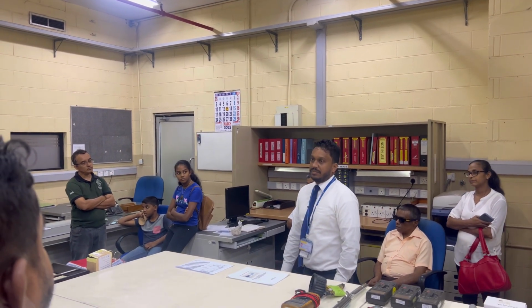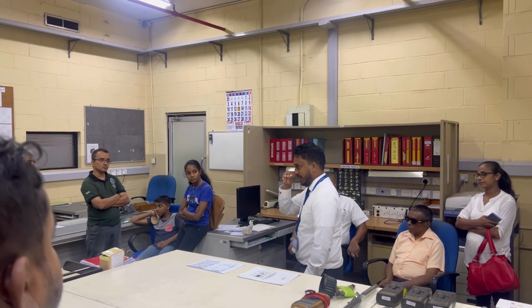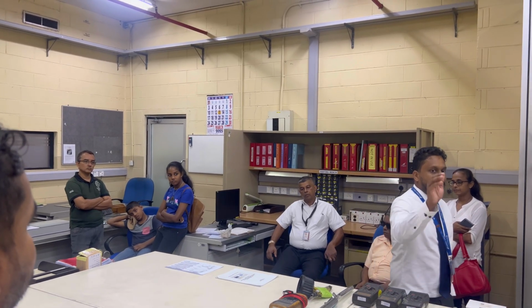That's why we have accreditation, not certification. So we are ISO 17025 accredited. That's the difference. We got the accreditation in 2018 for two cycles. We have accreditation for electrical parameters, sourcing, and we can calibrate instruments like multimeters, and even the voltage, mostly digital. And then the sourcing side, power supplies, and any source that has a voltage output, we can measure and give an accredited certificate. And then we have pressure calibration.